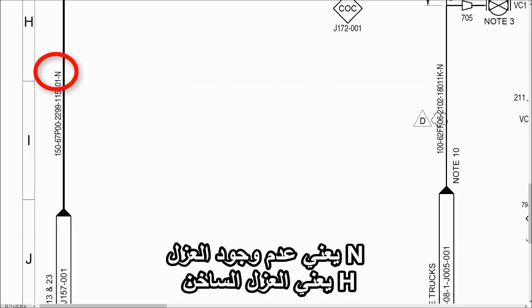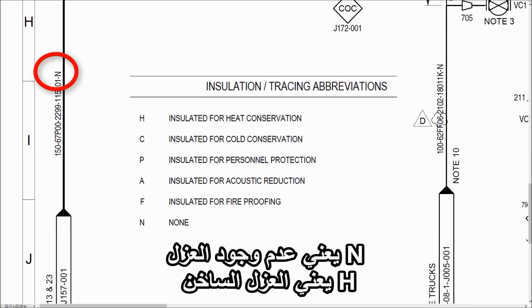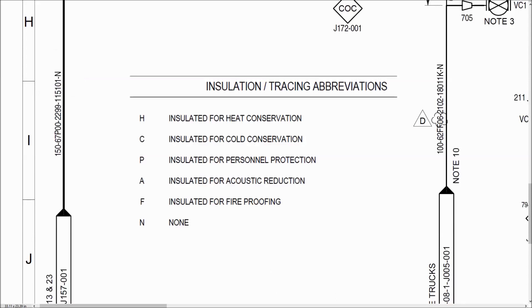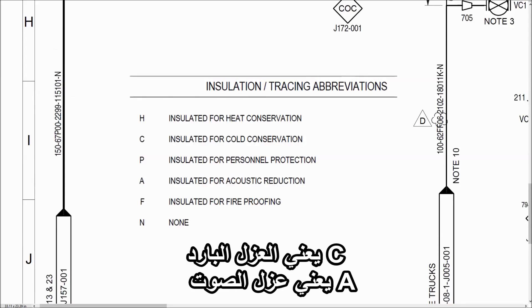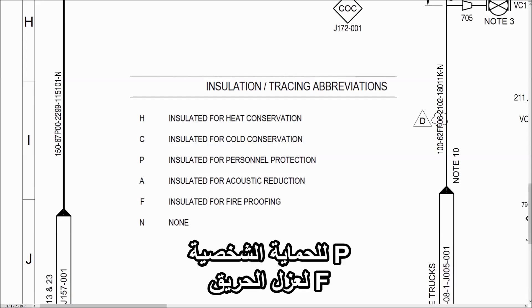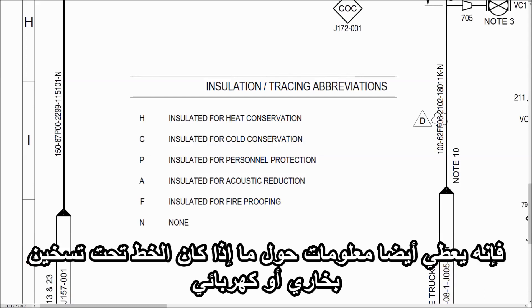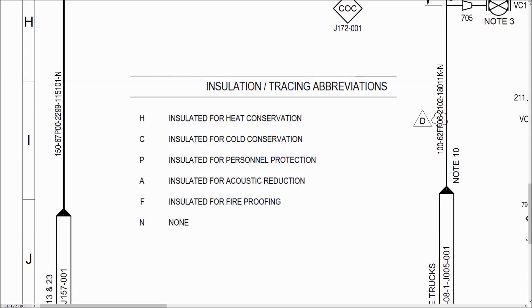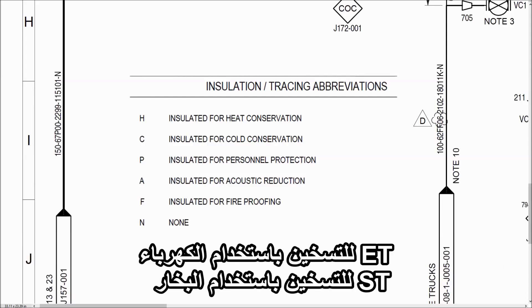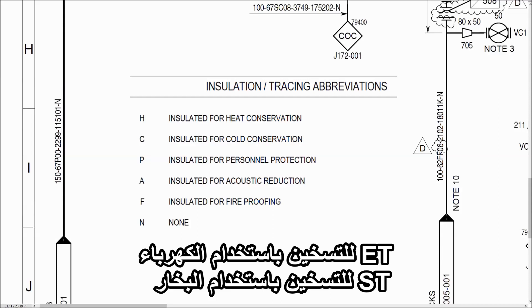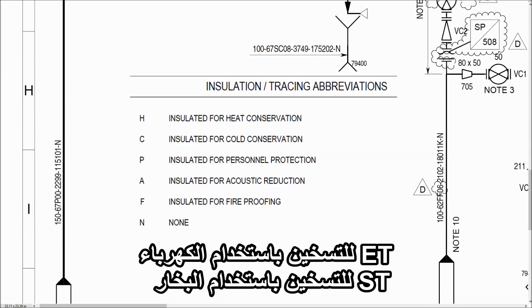Here, N means there is no insulation. If there is H, then hot insulation; C is for cold insulation; A for acoustic reduction; P for personal protection; F for fireproofing. It also gives information about whether the line is steam traced or electrically traced. Normally ET is used for electric tracing and ST is used for steam tracing.